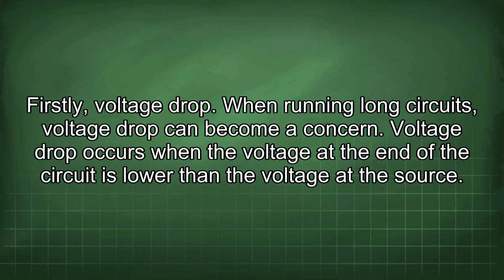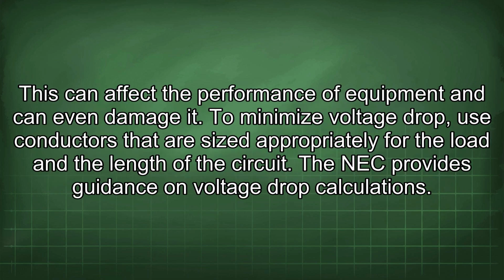Firstly, voltage drop. When running long circuits, voltage drop can become a concern. Voltage drop occurs when the voltage at the end of the circuit is lower than the voltage at the source. This can affect the performance of equipment and can even damage it.